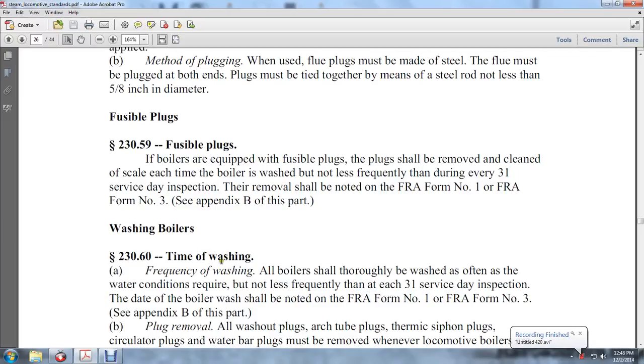Washing the Boiler: Time and Washing Frequency. All boilers shall be washed as often as water condition requires, but not less frequently than each 31 days of service to the boiler.